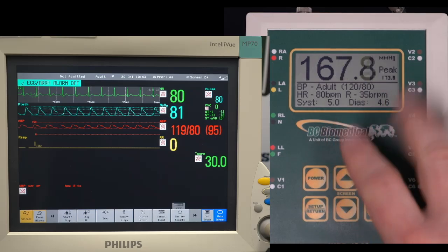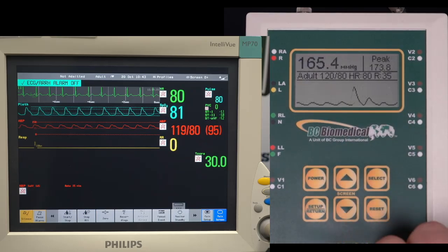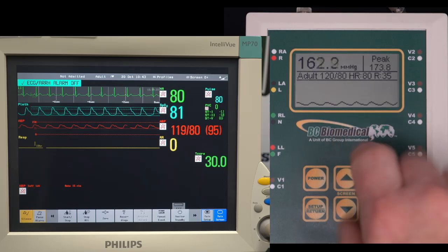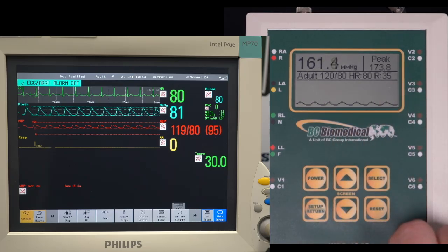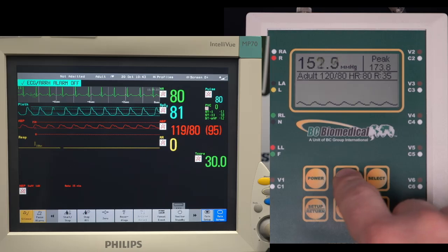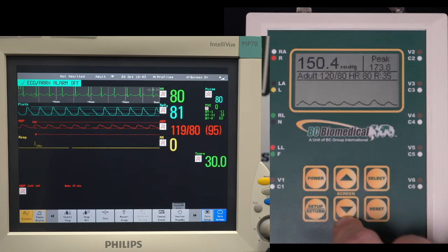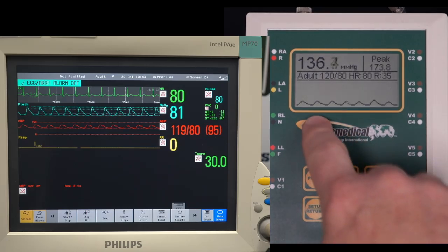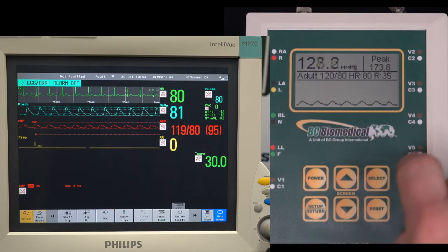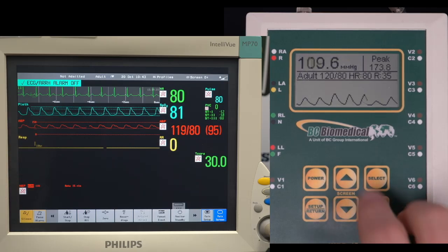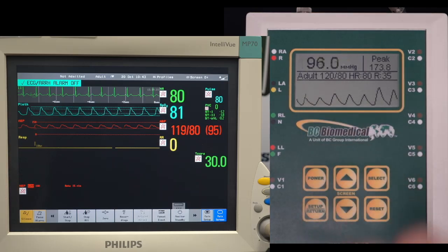Now, I don't know if you can hear it, but in the background I can hear the mechanism inside, the motor that's doing the blood pressure simulation. If we hit the down arrow, we'll change the screen that is selected. So now I can see what's actually happening in my simulation here. And as the monitor changes the pressure, the simulator will adjust its output accordingly and produce the output that we need for the monitor to read that.